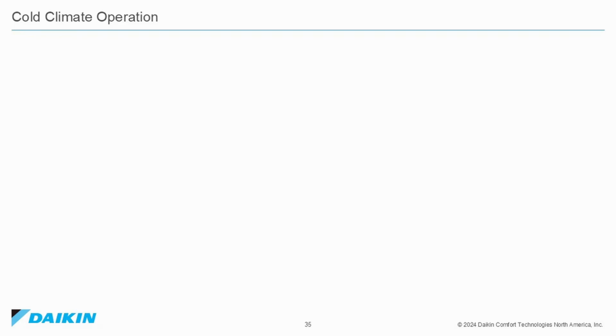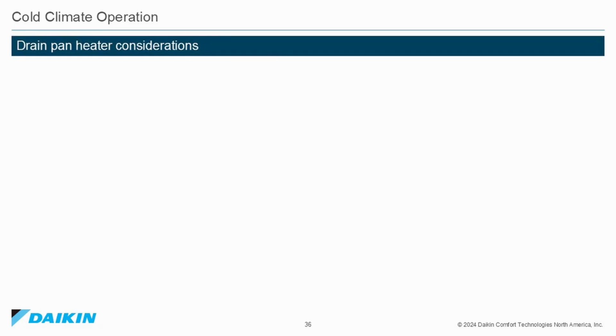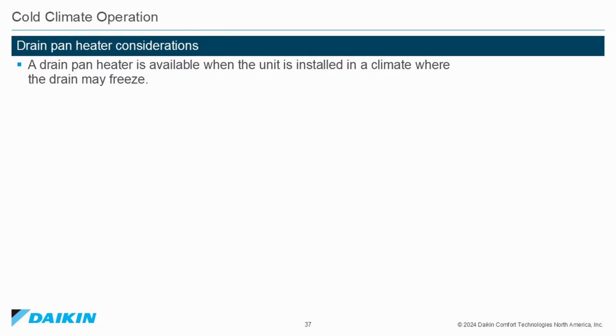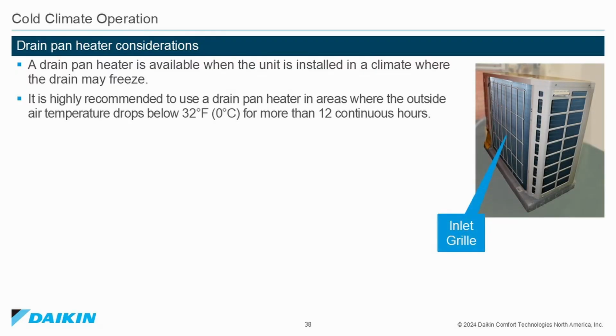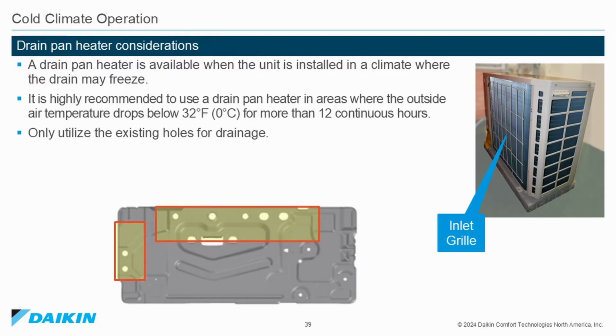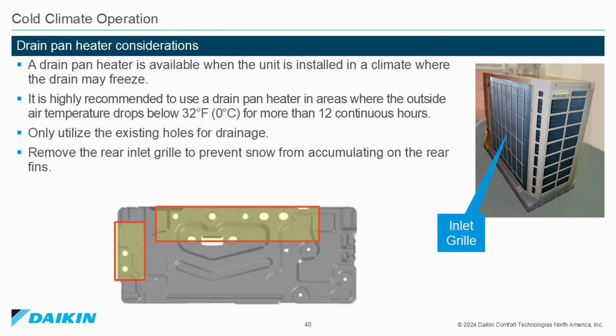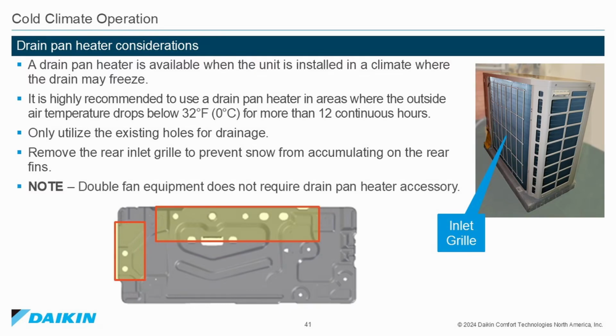Cold climate operation. Drain pan heater considerations. A drain pan heater is available when the unit is installed in a climate where the drain may freeze. It is highly recommended that you use a drain pan heater in areas where the outside air temperature drops below 32 degrees Fahrenheit for more than 12 continuous hours. Only utilize the existing holes for drainage. Remove the rear inlet grill to prevent snow from accumulating on the rear fins. Double fan equipment does not require a drain pan heater accessory.